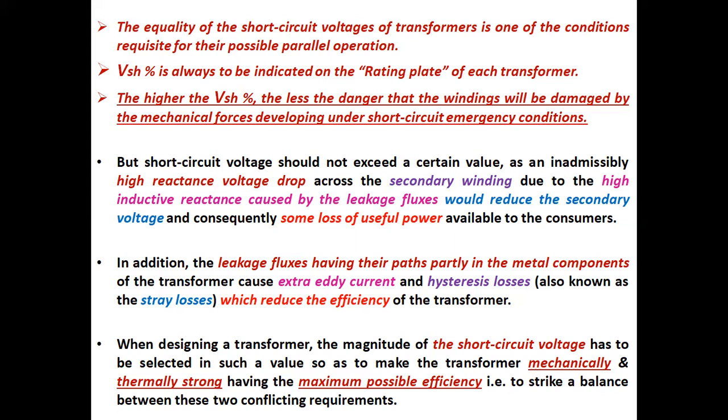In addition, the leakage fluxes having their paths partly in the metal components of the transformer cause extra eddy current and hysteresis losses, also known as stray losses, which reduce the efficiency of the transformer.